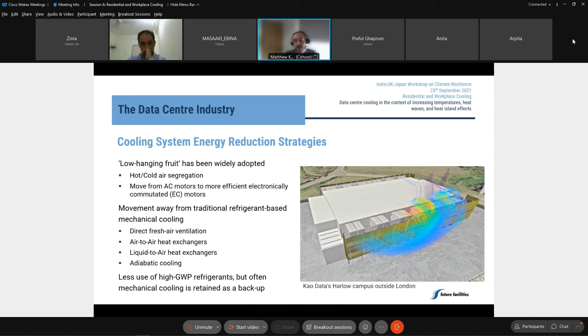But that isn't really the norm to use them in isolation. Often the refrigerant-based cooling is retained as a backup option, typically in case the weather outside gets too warm for the more efficient cooling options to work effectively. Some cooling systems actually have multiple cooling technologies built in, and then cost functions within their controllers to help select the most efficient and effective mode of operation depending on the ambient conditions outside. So next we'll move on to looking at how a warming climate will impact energy and water use, and the data center more generally.